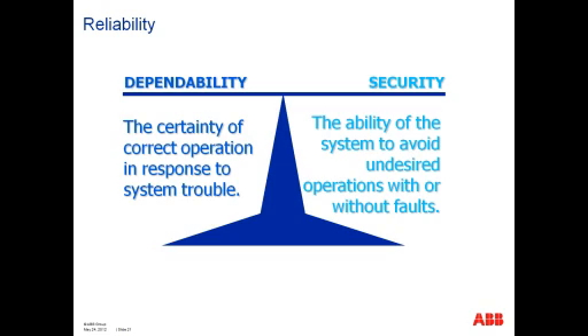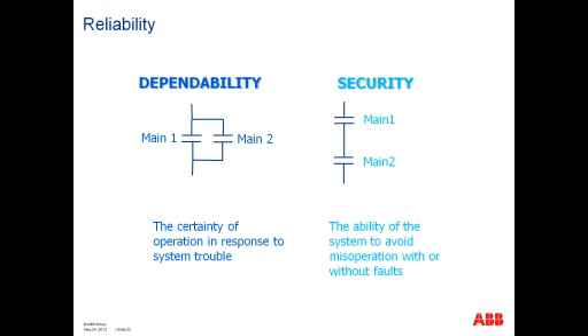Let's talk a little bit about reliability, because important in your jobs, of course, is providing reliable protection. And it's a balance between dependability and security. Dependability is the certainty of correct operation in response to system trouble. You want to be certain that you've detected the event. And then security is the ability of the system to avoid undesired operations with or without fault.